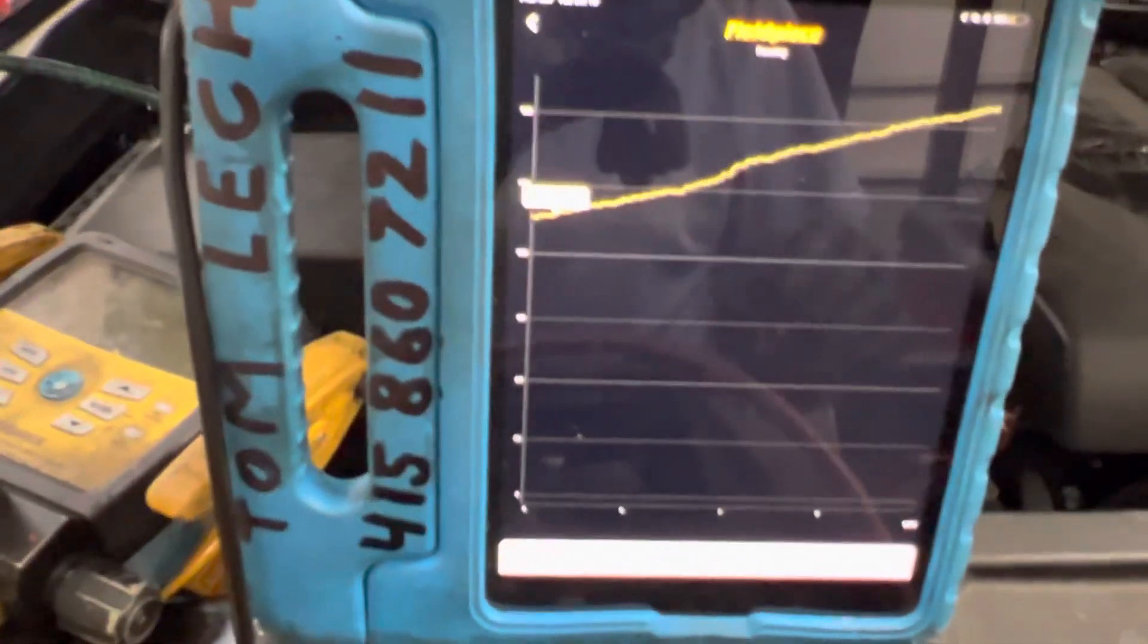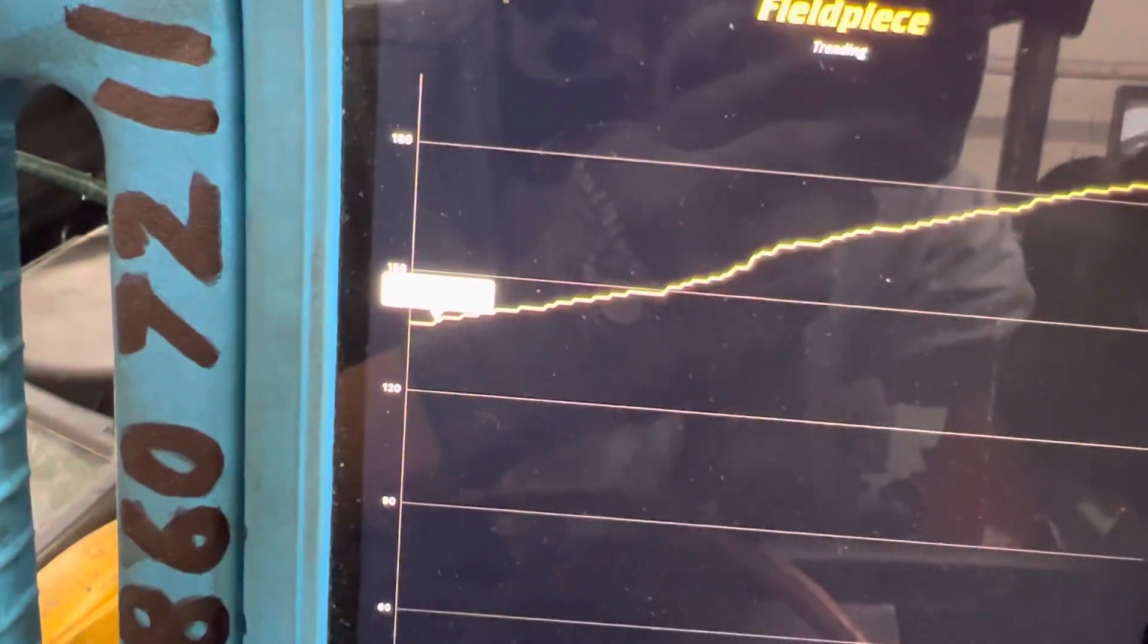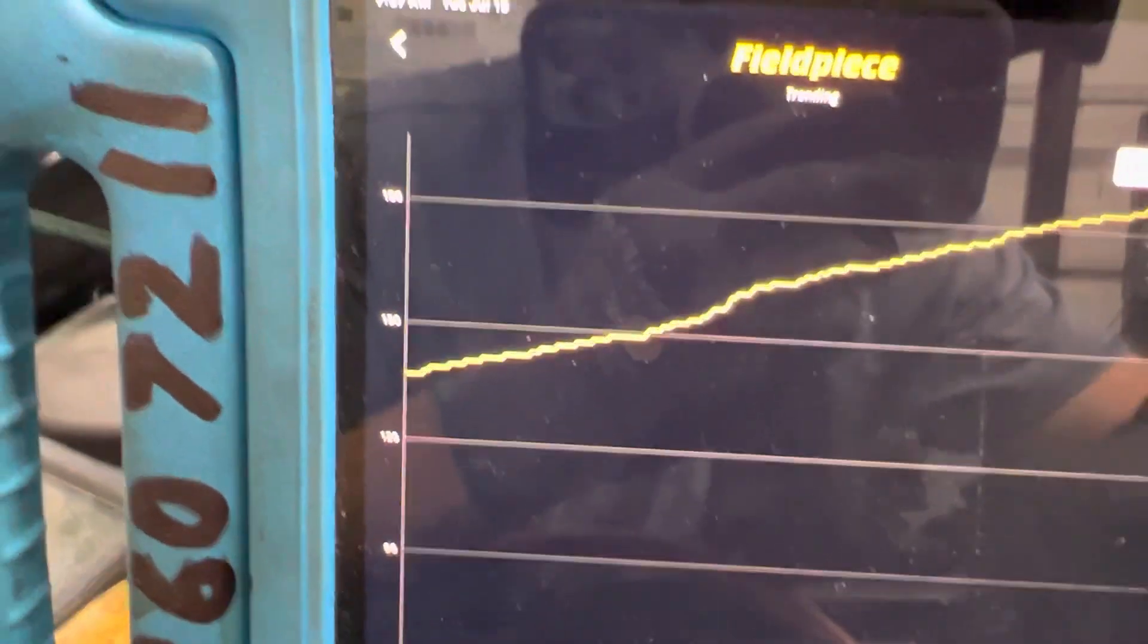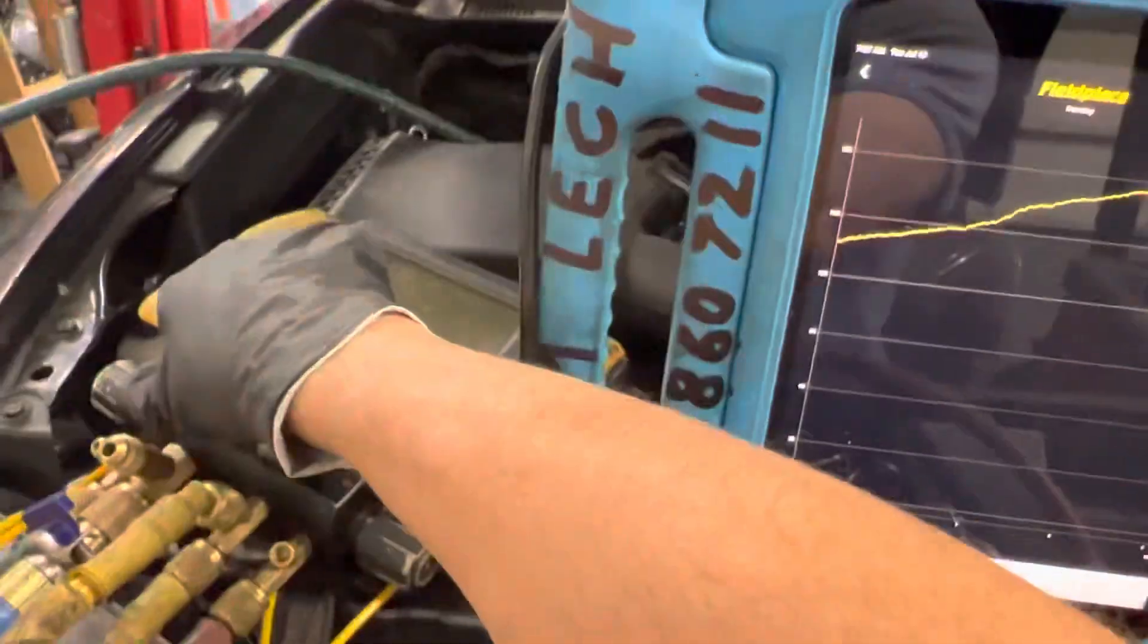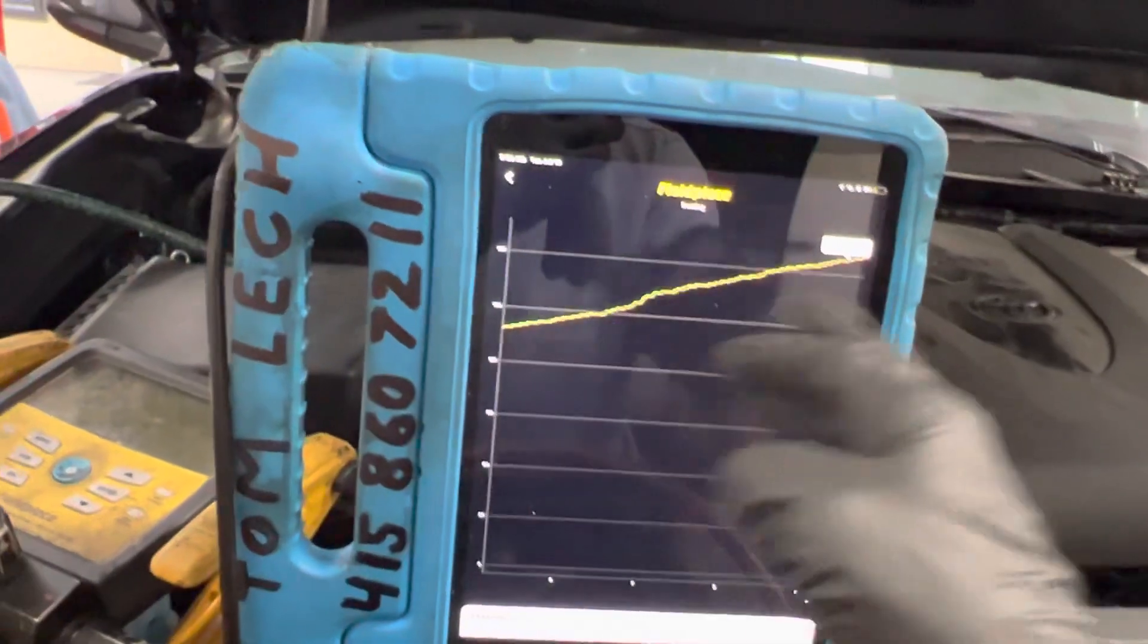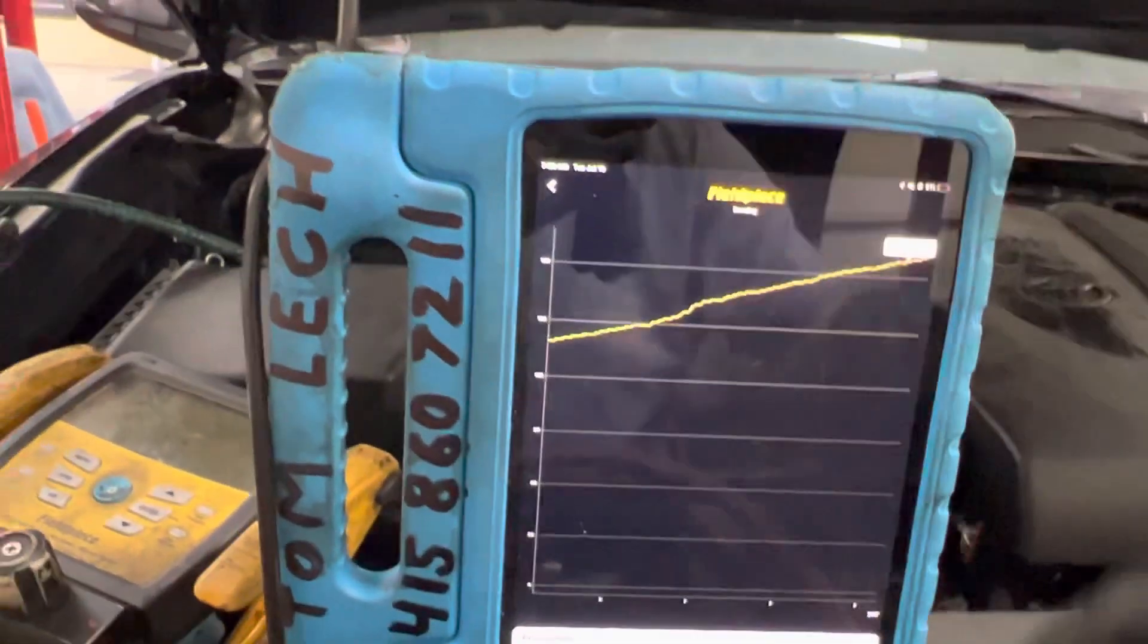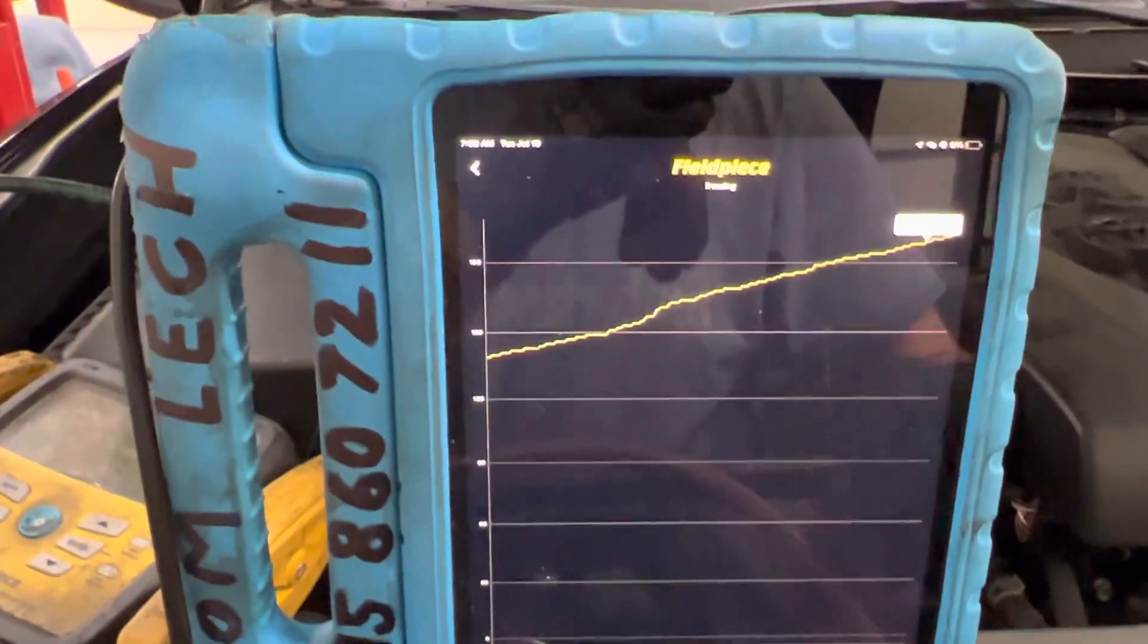I've got to charge this up and get out of here. As you can see, we are up to 189 microns with the vacuum turned off, and I'm reading through hoses, which is accounting for the majority of the loss of the micron decay. All right, see you.